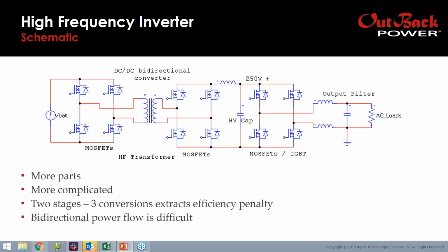With this high frequency inverter, bidirectional power flow is possible, but it's actually difficult because of limitations. And again, because of the 3 conversions, the efficiency of this type of inverter is lower than that of a low frequency inverter, because it's 3 power conversions, and the overall efficiency is a product of each conversion. So even if you have 2 converters that have 90% efficiency, the overall output efficiency is only 81%. So to get 90+ percent efficiencies, you need power stages that are nearly 100%, in the 98% range. To get an output efficiency of 95% with 2 conversions, you'd have to have 2 converters at 98%, which means it's a more expensive inverter than it would be otherwise.